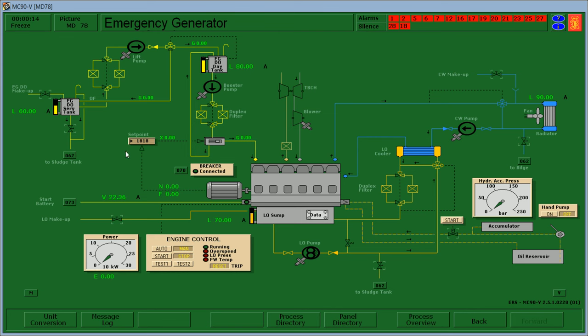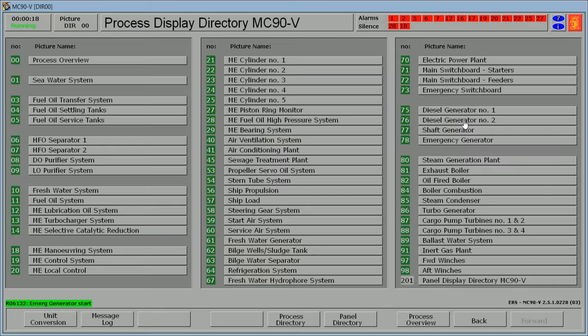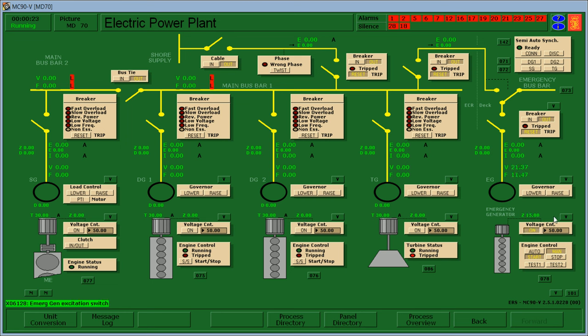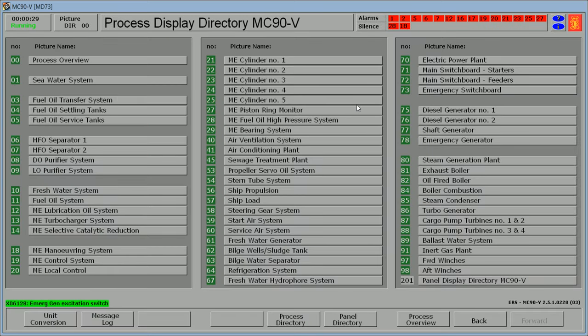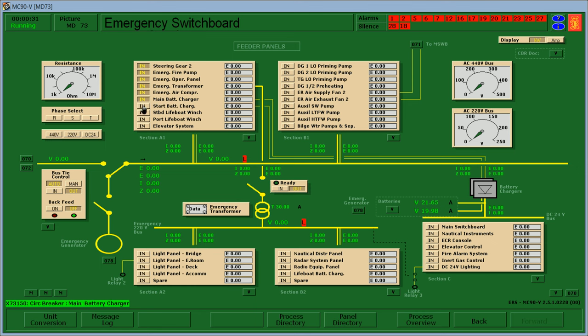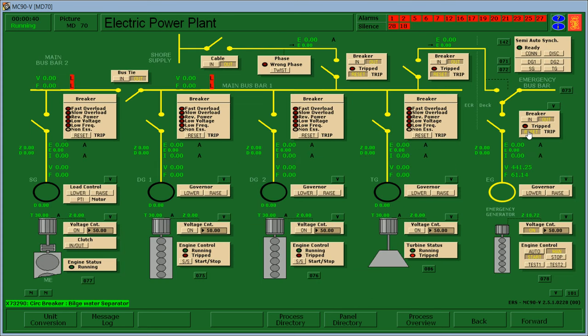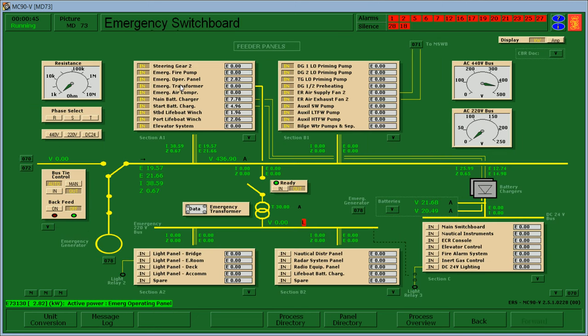So we first go to the emergency generator and press start. When the emergency generator starts, proceed to electric power plant, open the voltage control. While the engine is starting up, we first ready the emergency switchboard, open the circuits. Now when you hear the engine is fully running, we close in the breaker. Then proceed again to the emergency switchboard and turn on all the switches.